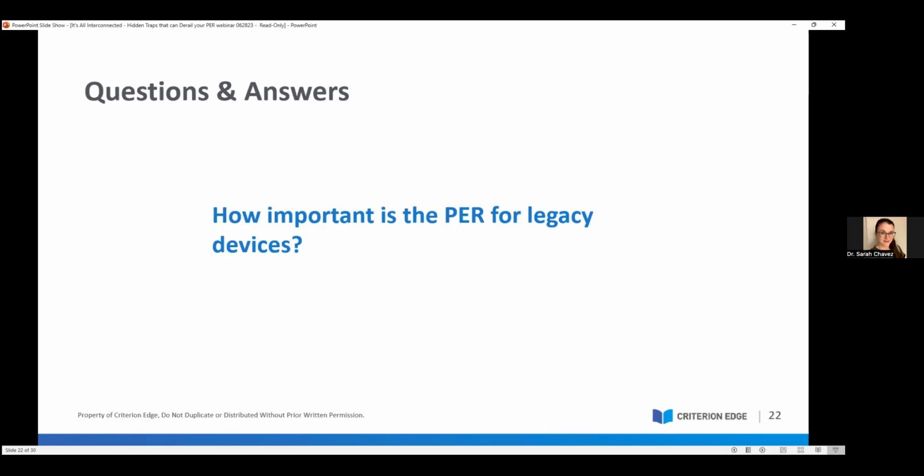That's what they're really trying to assess here. Not everything is going to make it through the IVDR in its existing form, but that's their purpose. They want to ensure that your device performs as intended under whatever specific circumstances you're claiming. So it is possible for you to go in and say, I'm not the most sensitive test on the market, but maybe I have the benefit of being able to be used at point of care, or I can be used under these very specific circumstances, and this is where people are using my device still.